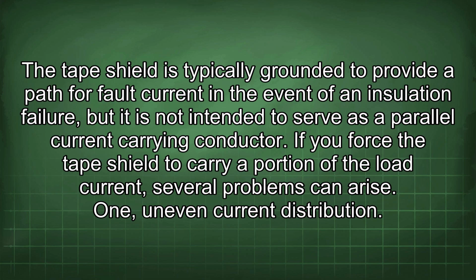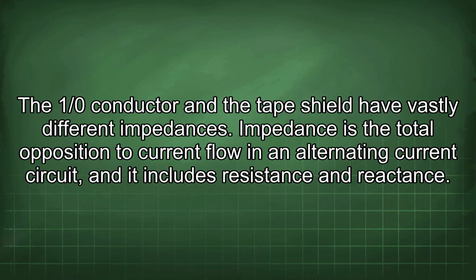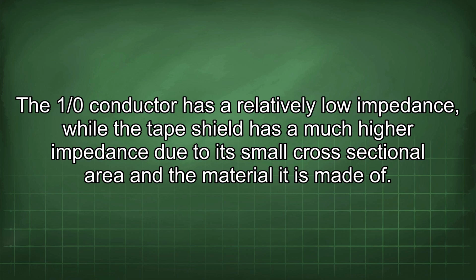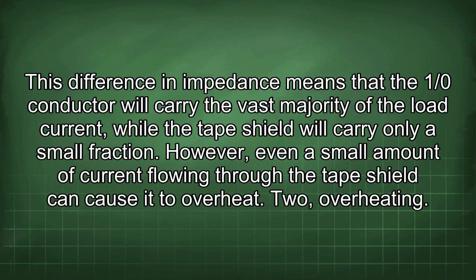1. Uneven current distribution. The 1/0 conductor and the tape shield have vastly different impedances. Impedance is the total opposition to current flow in an alternating current circuit, and it includes resistance and reactance. The 1/0 conductor has a relatively low impedance, while the tape shield has a much higher impedance due to a small cross-sectional area and the material it is made of. This difference in impedance means that the 1/0 conductor will carry the vast majority of the load current, while the tape shield will carry only a small fraction. However, even a small amount of current flowing through the tape shield can cause it to overheat.